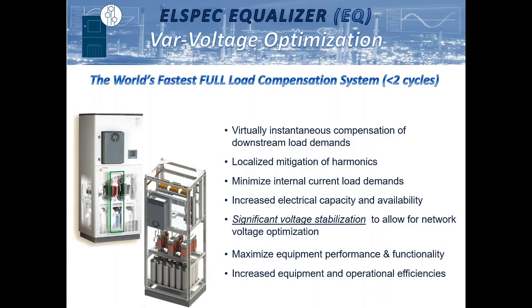So by doing so, we can switch in as many groups as we need, or we can take out as many groups as we need, virtually instantaneously. So our typical full load demand response is less than one cycle. So we measure and calculate in less than a quarter of a cycle, and then we wait for the voltage waveforms to cross.